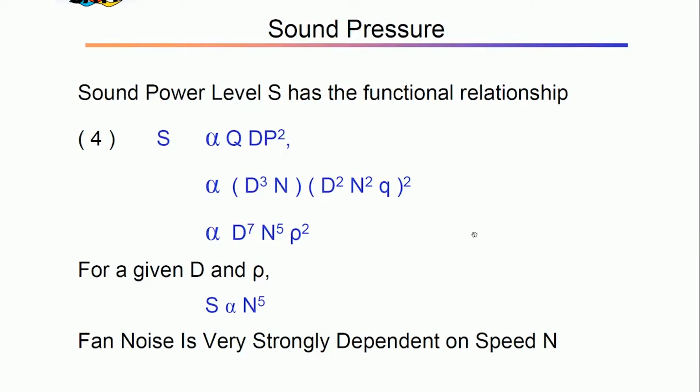So, at very high velocities, if you take a standard extrusion, fin effectiveness comes down. So, beyond a certain point, that is where Schoenhauser mentioned, do not exceed 6 meters per second. Beyond that, it does not seem to make any difference, except it is already neatly packaged and so on. So, they have given things like noise is dependent on speed.